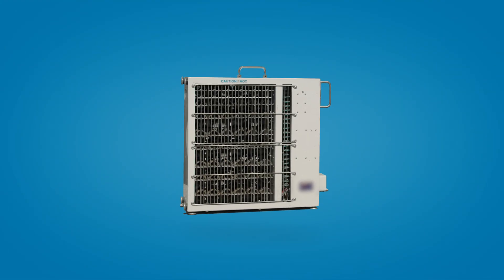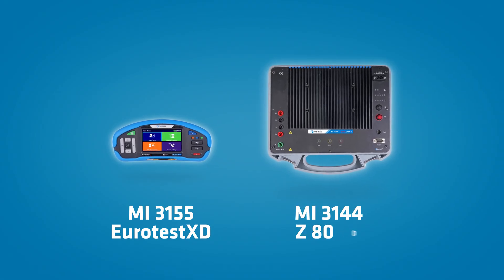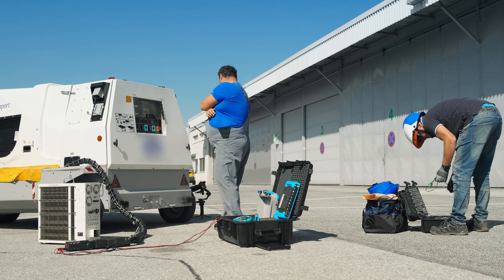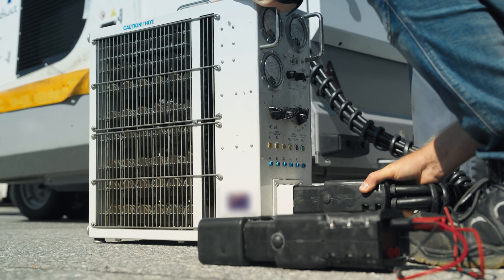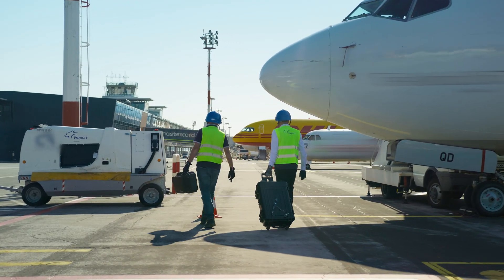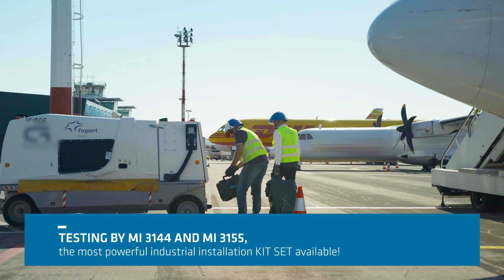Testing can be done using a resistive load, or a combination of the MI3155 Eurotest XD and MI3144 Z80. The resistive load approach only tests the ground power unit's ability to deliver power by measuring the current through the resistive load. The alternative is using our testers, which are also easily portable and can be used for a wide array of testing applications.